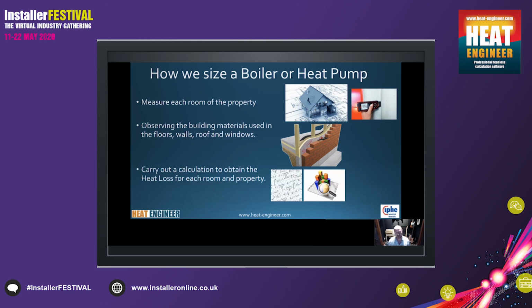We need to carry out this calculation to obviously find the heat loss for each room and property, and it's getting more and more important to do so as we start zoning off different areas, etc. And we need to obviously calculate the flow rates out for those to make sure that your boilers and your heat source, whatever it is, is sitting in its sweet spot. I mean, we don't care what the heat source is. We're moving more and more towards renewable technologies now, and I think this is more important, certainly with heat pumps.